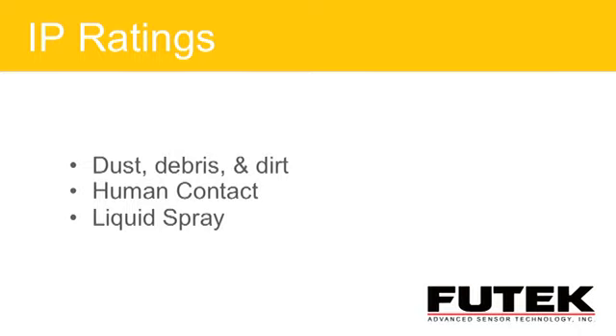Our focus is really on different environments - dust, debris, dirt. Are there requirements where it could affect our product's capabilities? Is there dirt, and do we have an overload stop, which we'll show you in a minute on a product? Is it going to get dirty, and will that affect what you're trying to perform? Also consider liquid spray - is it going to be sprayed in such a way? One thing you could do is ask your salesperson what IP rating is needed to meet your requirement.